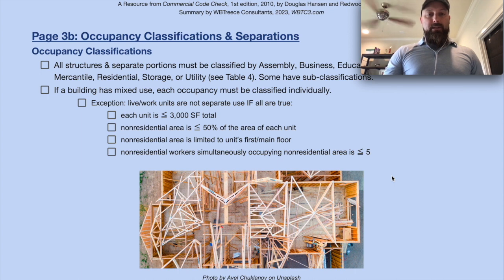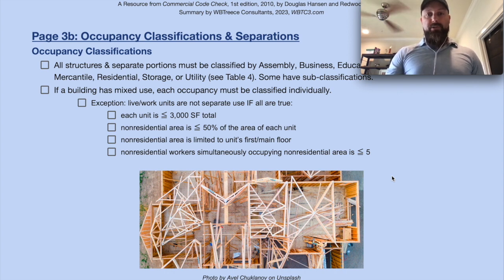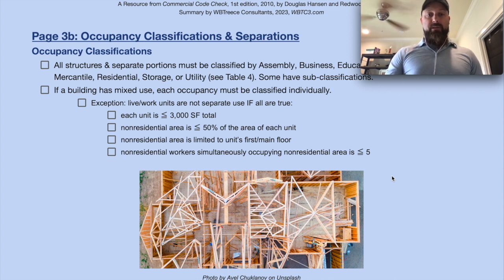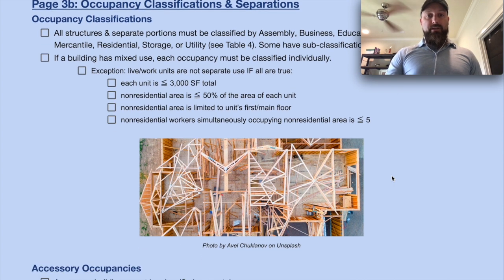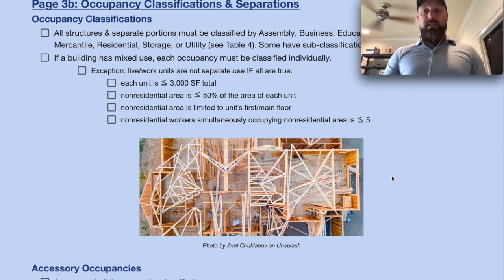If a building has a mixed use, each occupancy must be classified individually. There is an exception for live-work units — they're not considered separate use if the following four things are true: each unit must be less than or equal to 3,000 square feet total; the non-residential area must be less than or equal to 50% of the total area; the non-residential area is limited to the unit's first or main floor; and non-residential workers simultaneously occupying the non-residential area must be less than or equal to 5.